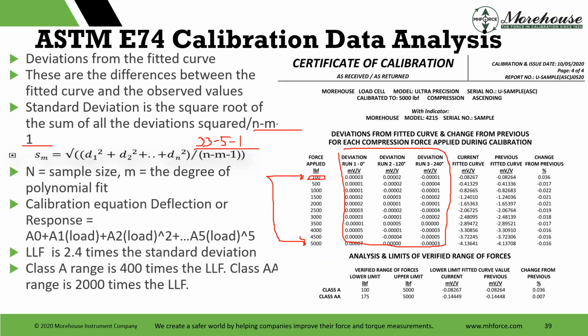multiply. The lower limit factor is 2.4 times the standard deviation, and we get that by figuring out our resolution again, because we're in millivolts. We're going to get a standard deviation in millivolt, and we're going to convert it to, in this case, LBF. So we're going to multiply it.